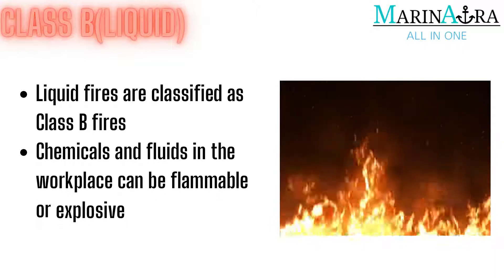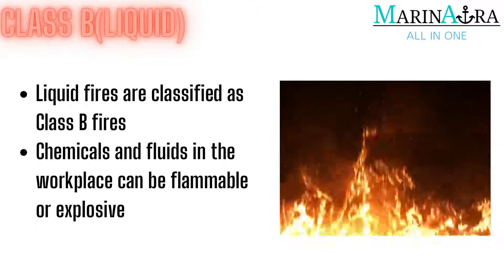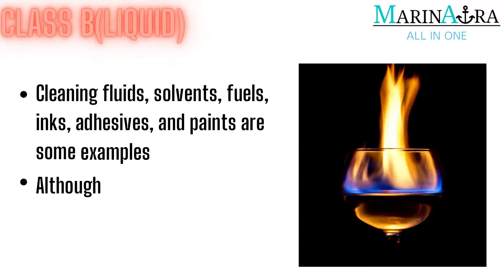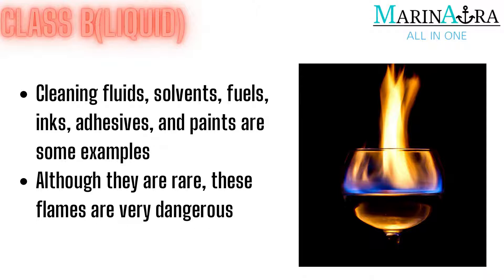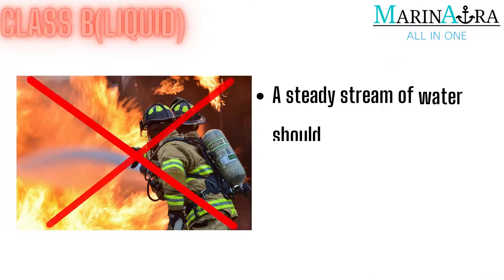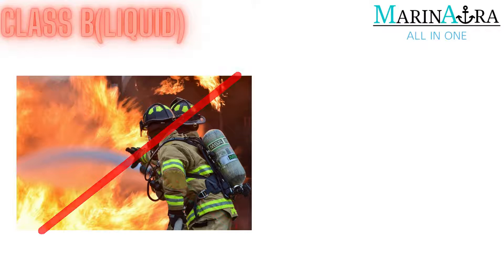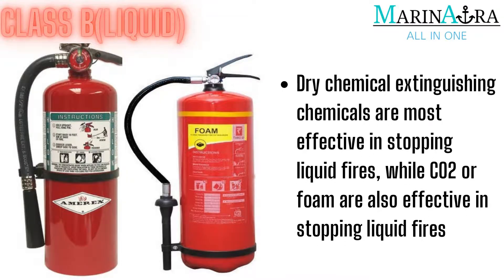Class B — Liquid. Liquid fires are classified as class B fires. Many fluids, liquids, and chemicals used in the workplace have the potential to be flammable or explosive. Cleaning fluids, solvents, fuels, inks, adhesives, and paints are just a few examples. These flames are rare, yet they are more dangerous than other types of fire. This type of fire should never be put out with a steady spray of water because it can scatter the fuel, spreading the flames. Extinguishing a liquid fire by blocking the fire's chemical chain reaction, as done by dry chemical and halon extinguishing agents, is the most efficient method. However, smothering with CO2 or, for liquids, foam is also useful.